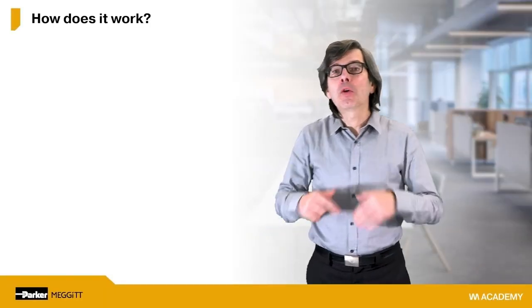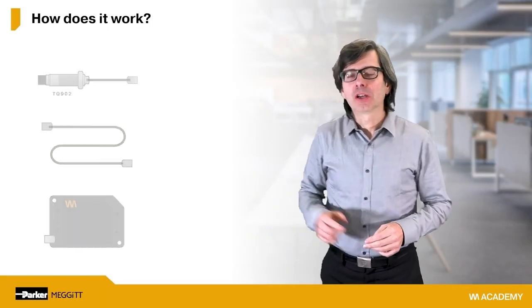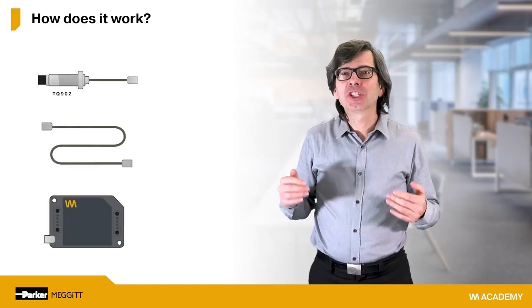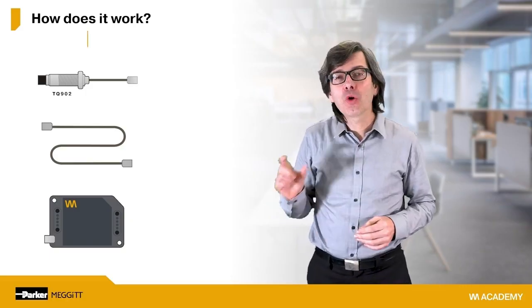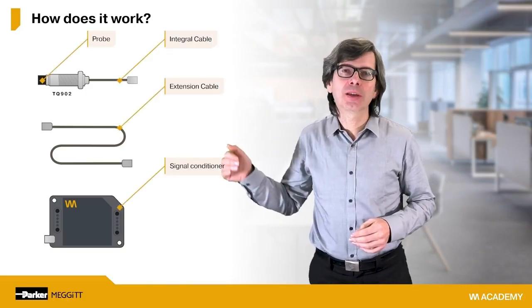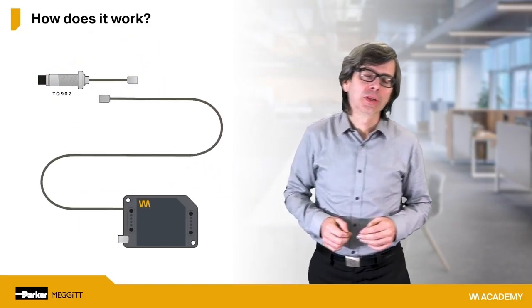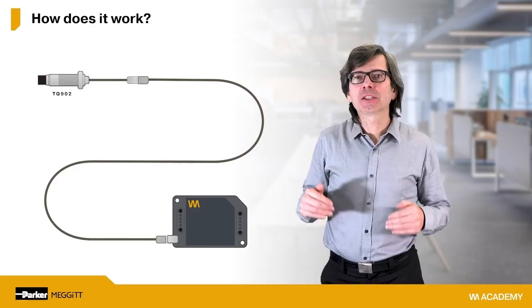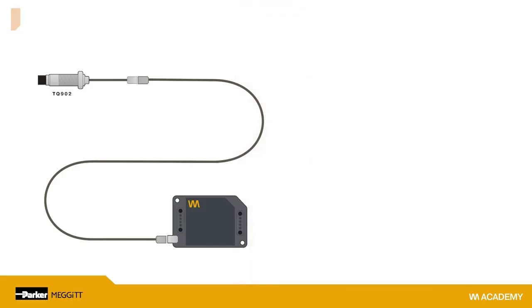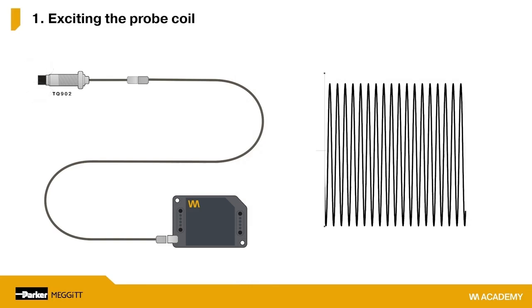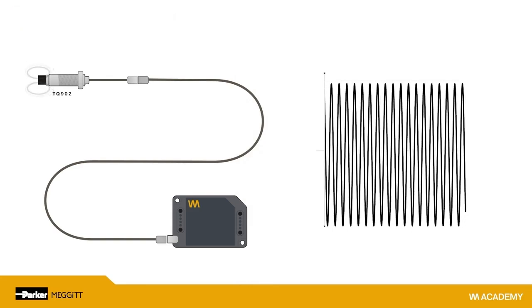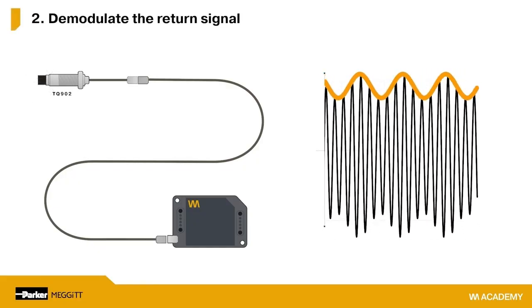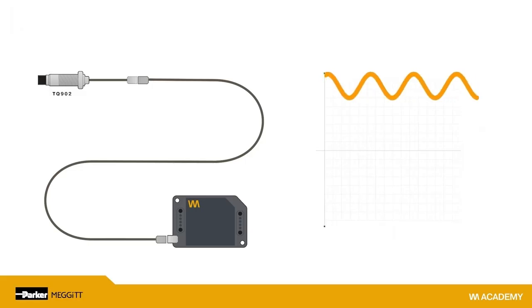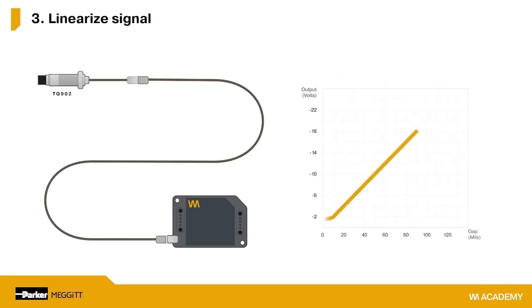Let's have a look now at the complete probe system. As you can see on this drawing, the probe system consists of 3 basic components: the probe and its integral cable, the extension cable, and the signal conditioner. The signal conditioner has 3 fundamental tasks. First, to excite the probe coil so that it emits an electromagnetic field, then to demodulate the return signal from the probe, and third, to linearize the signal so that a consistent gap versus output relationship is maintained across the linear range.